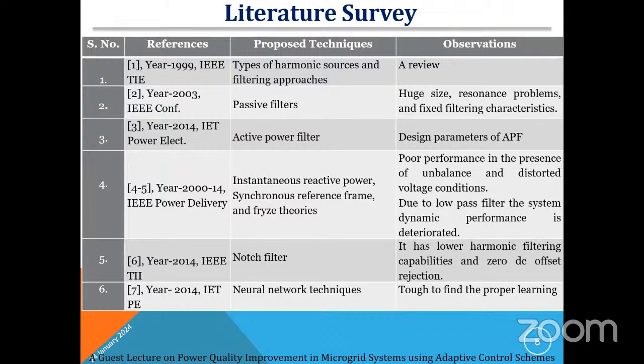If you use a shunt active power filter, we can remove the current harmonics. If you use a series active power filter, we can remove voltage harmonics. If you use a hybrid active power filter, we can remove both current and voltage harmonics. And in this particular paper, they have given the design parameters of how to design shunt, series, and hybrid active power filters.